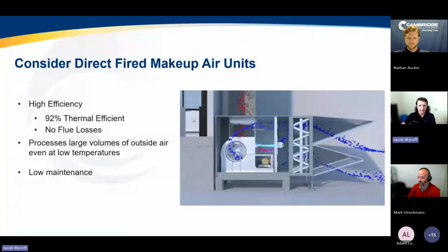Another huge reason that they're used in these applications is that they're able to process large volumes of outside air, even at very, very low temperatures outside. So that's something that indirect fire technologies and electric technologies especially can sometimes struggle with, being able to provide the needed heat on the coldest day of the year.